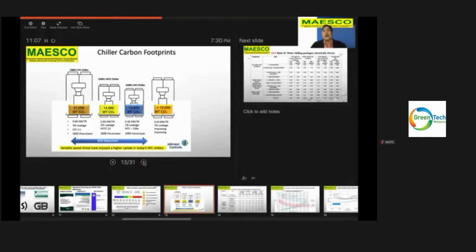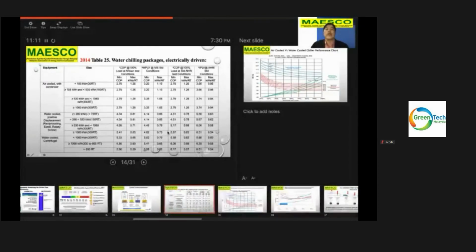And always look at Malaysian Standard table 25, water chilling packages, electrically driven, where it states what chiller to use at what percentage. Let's say, for example, if you're looking for a 500-ton chiller. Now, a 500-ton chiller falls here. That means 300 to 600 RT. You use a water-cooled centrifugal chiller. Always refer to Malaysian Standard 1525, 2014, table, because this table has already been vetted by most consultants and also the chiller vendors. They qualify themselves that these are all achievable standards.